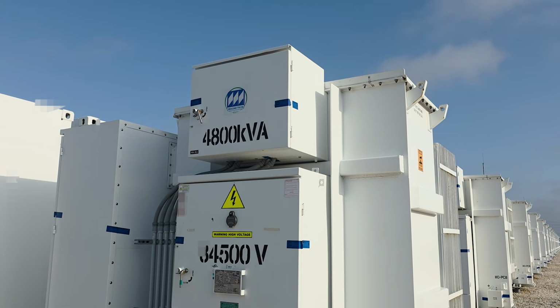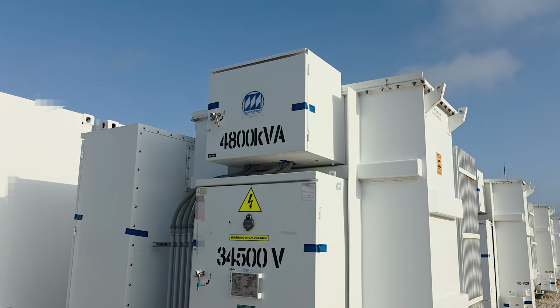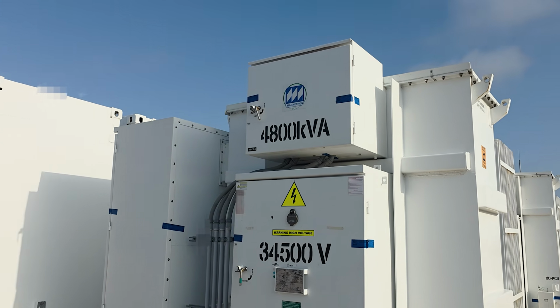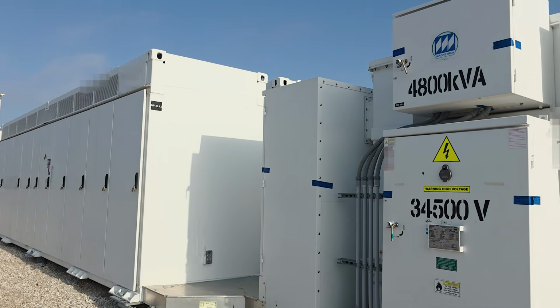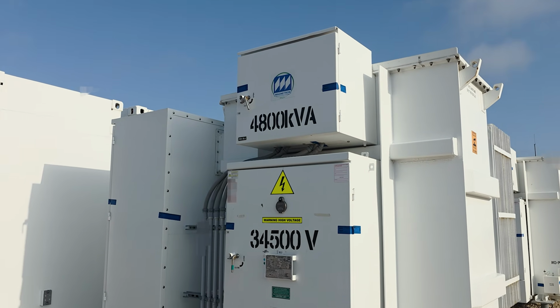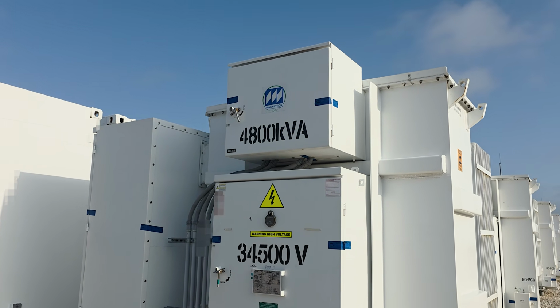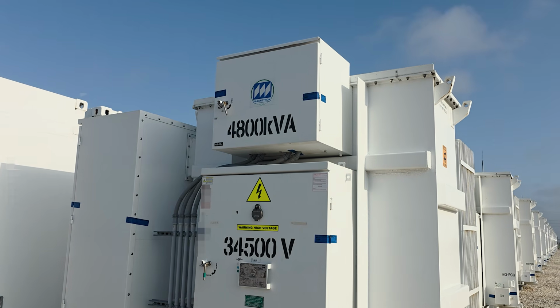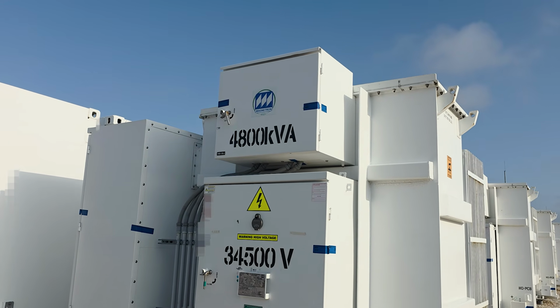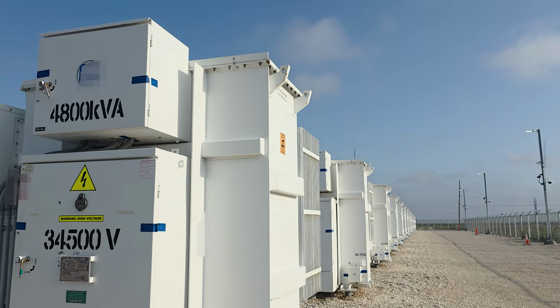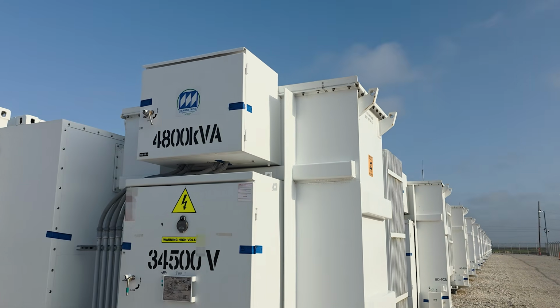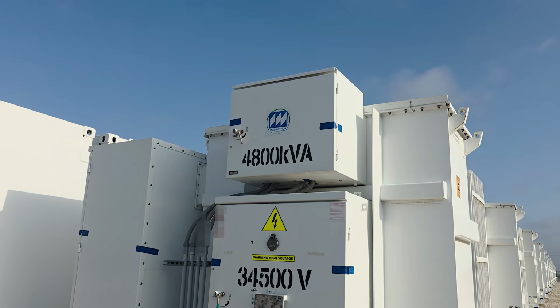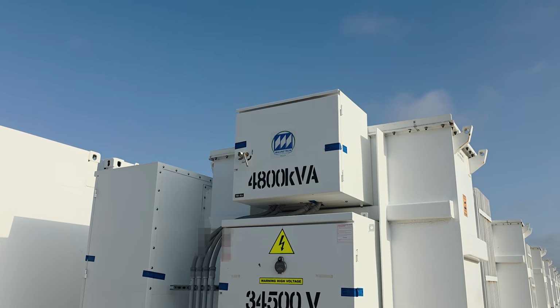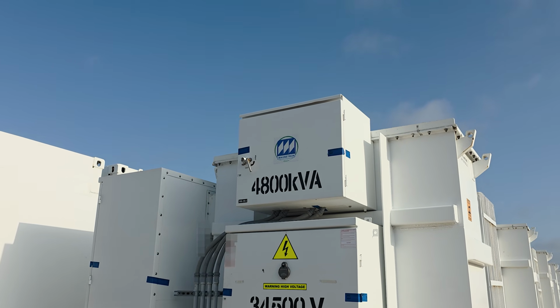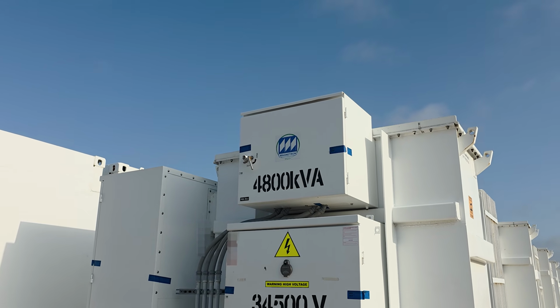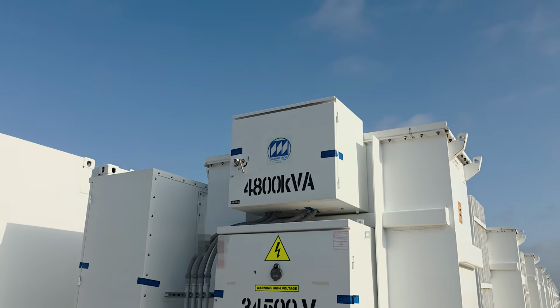It's not really necessary, but it will actually give you power and power quality data for each set of batteries. So it's a very advanced amount of monitoring. You don't need that much monitoring, but they want it. And if you want it, you can get it. So there's a 735 relay in each of these, which records your voltage, your amperage, phase angle, total kilowatts delivered, power factor. There's a ton. What else is in there?